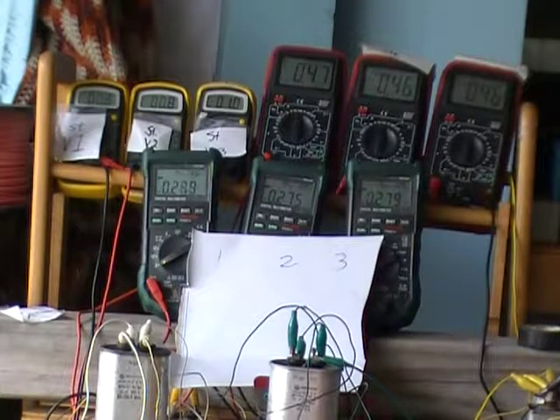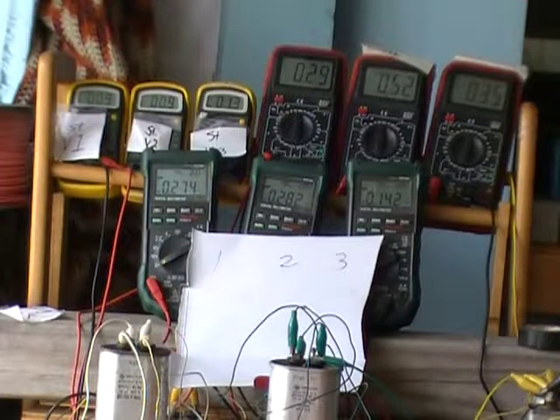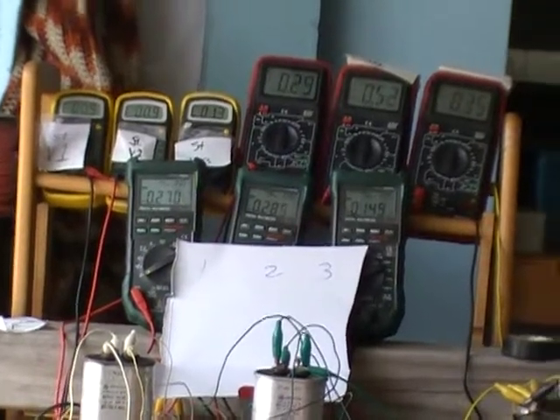Note the amperage on phase 3, 0.278. Phases 1 and 2 stayed relatively the same, but the amperage on phase 3 went down to 0.14.